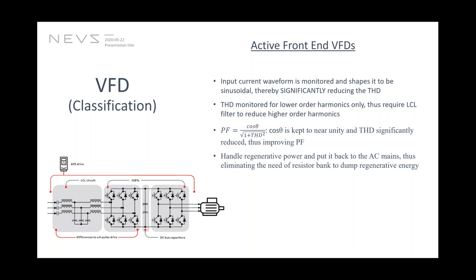Now, one interesting thing I found out was the power factor for this sort of application not only depends upon the phase shift between the voltage and current, it also depends on the total harmonic distortion. So cos theta, or the angle between voltage and current, can be kept near unity with this active front end, and the total harmonic distortion is also significantly reduced. That means it also helps significantly in improving the power factor.